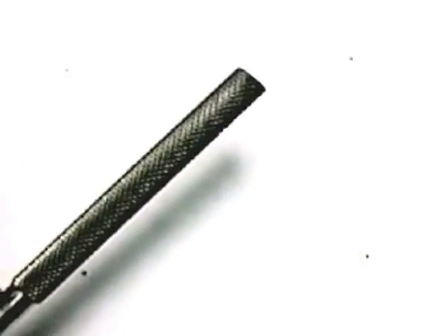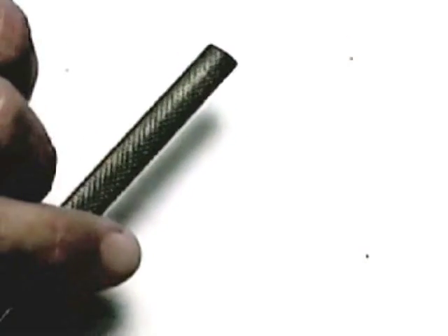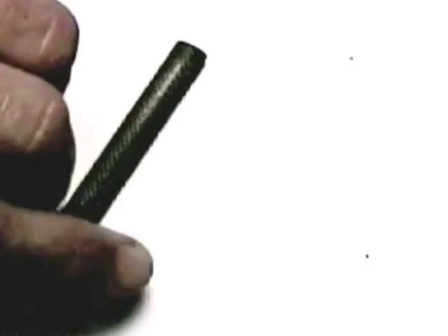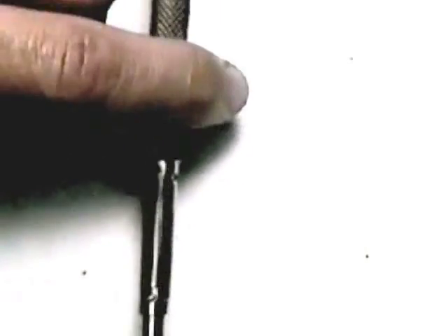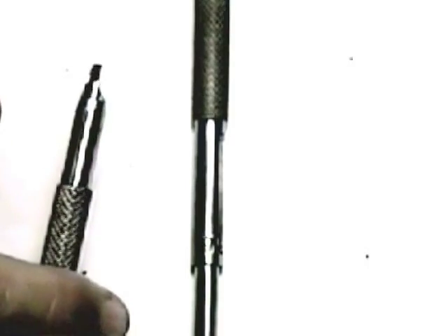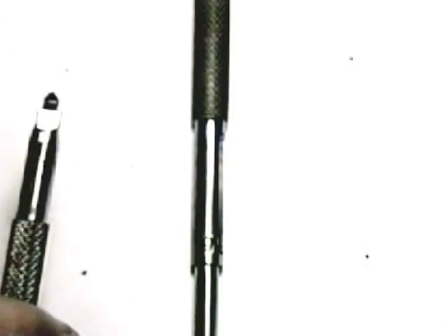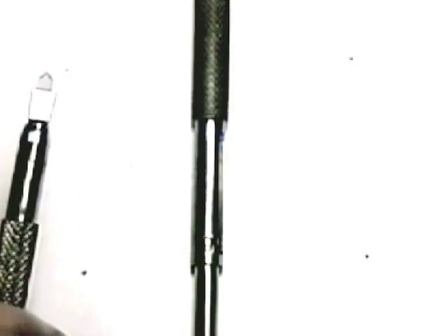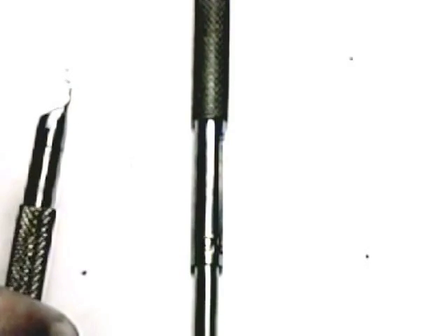Then the surgeon should retract it back into the housing and hand it off to the assistant. Most of the accidents that occur happen during the autoclaving process or when the blade is on the tray and other instruments are put on top of it. This causes all kinds of problems with blades chipping and so forth. So the key to the sterilization process is never allow anyone to touch this knife unless it's in the fully retracted position. Likewise with the step knife. You can see that it's in a fully retracted position now, so I would recommend that this knife be handed to the surgeon just like this, and then let the surgeon advance it to whatever setting that they want, and then when they're done, retract it back into the housing and hand it off to the assistant.